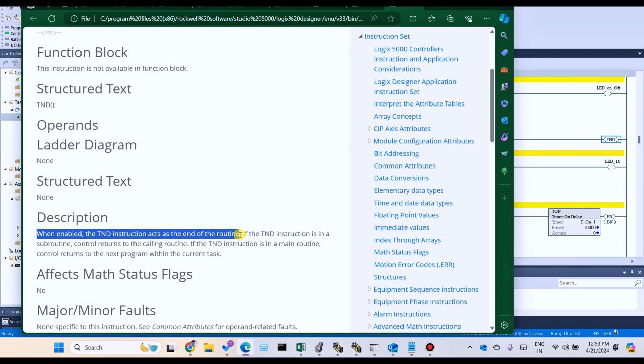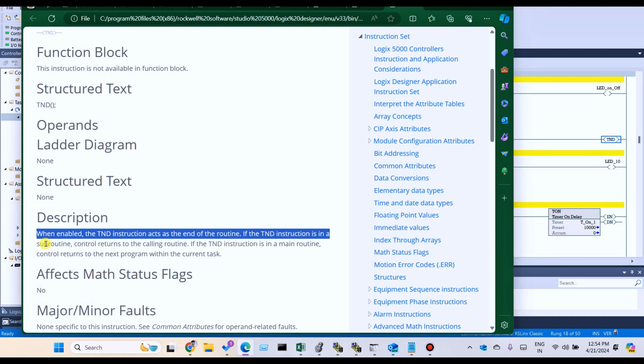We cannot use end routine. If we enable TND, all routines from TND to last routine will not operate. If that TND instruction is in a subroutine, control returns to the calling routine.